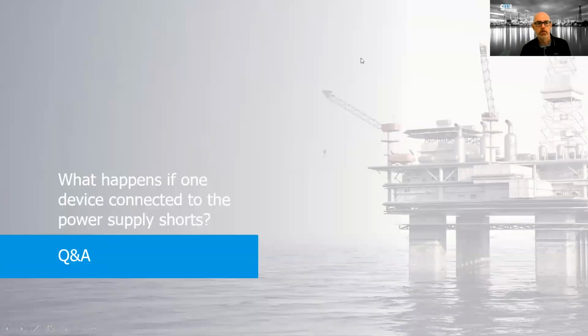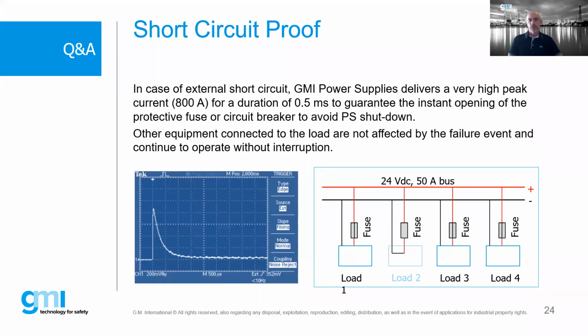Okay. Well, Andrea, to conclude our presentation, what happens if one device connected to the power supply shorts? This is a specific feature we implement. In case of a short circuit, if you have the power connected to different loads, this kind of power supply is able to deliver a very high peak of current. We are talking about 800 amps for a very short duration, 0.5 millisecond, and this is enough to guarantee the instant opening of the protective fuse or circuit breaker.